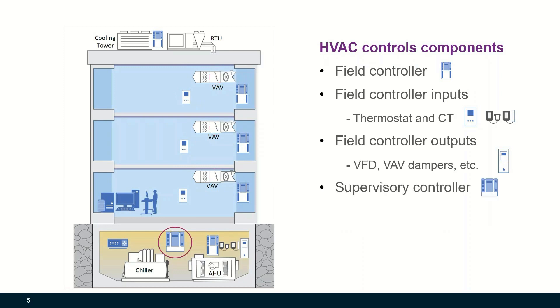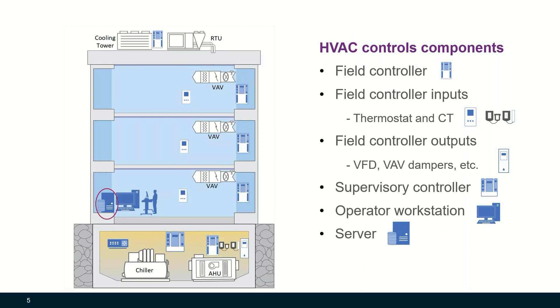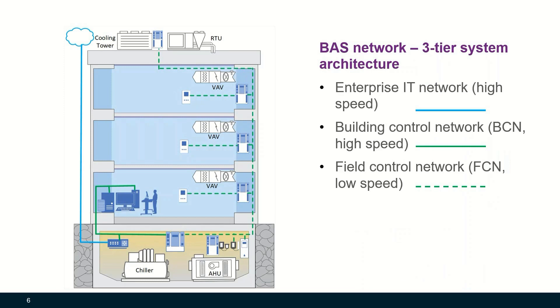There's another type of controller called a supervisory controller. And then you have an operator workstation, a server, and a network communication interface. Modern building automation systems are networked systems. In this three-tier system architecture, there are the enterprise IT network (blue line), building control network (green line), and the field control network (dotted green lines).